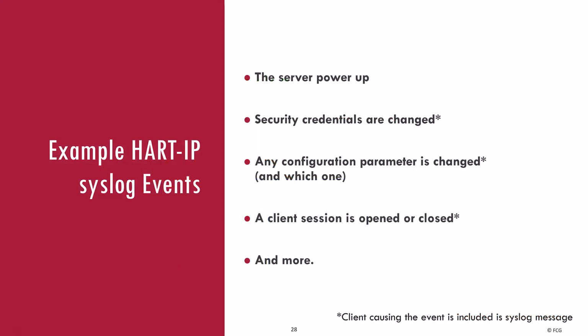HART-IP specifies a diverse group of events that must be published by devices. These include things like when the server powers up, whenever somebody changes security credentials, whenever a session is opened or closed, whenever a configuration parameter is changed, and which configuration parameter in particular. All these are timestamped. If a client is triggering the event, then the IP address of that client is also included. And so these are a lot of different diagnostics that are published, and it allows you to kind of backtrack through what's going on.